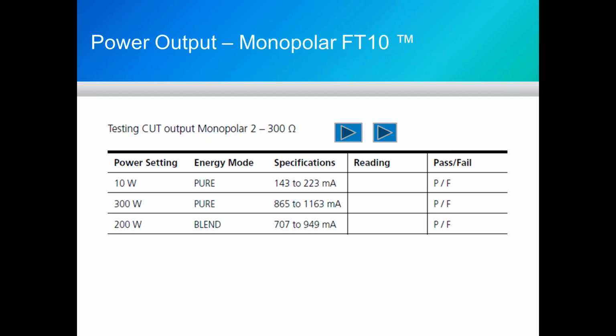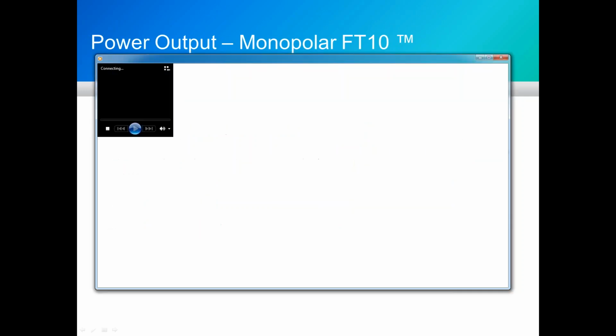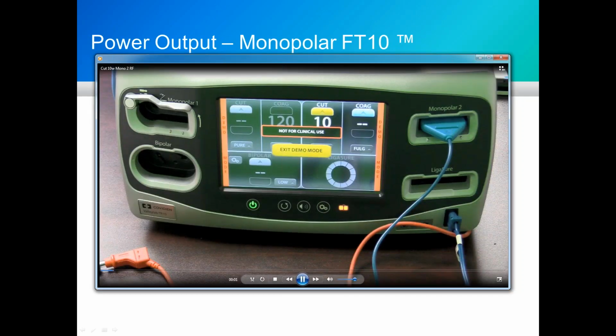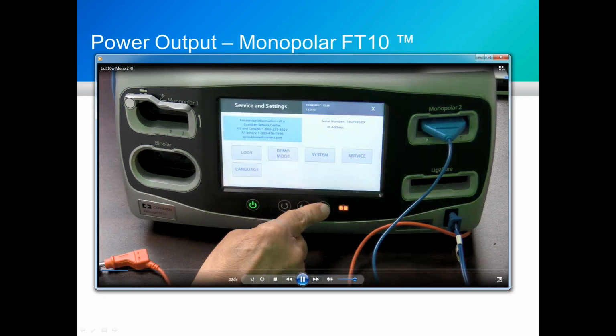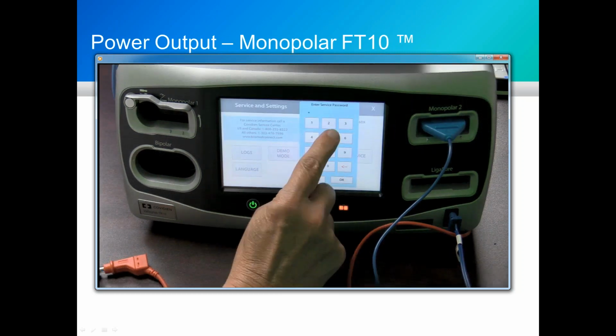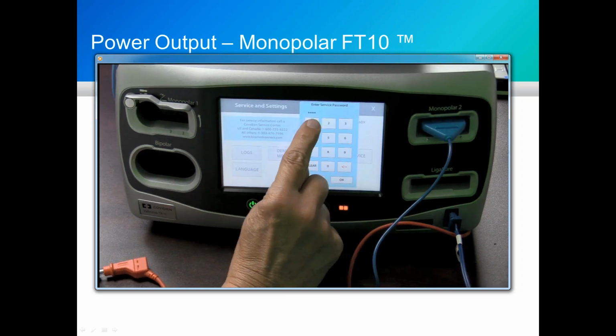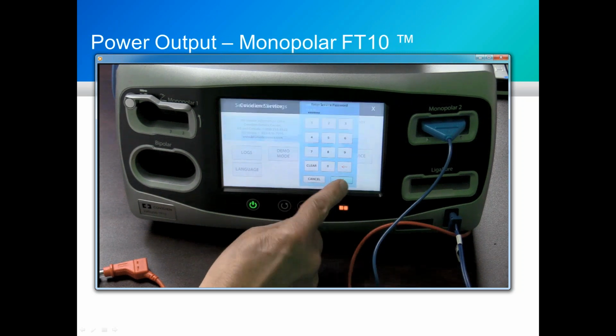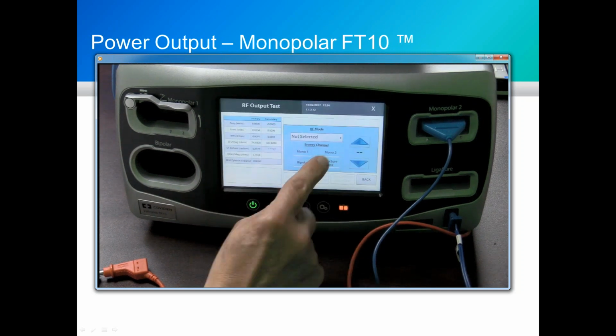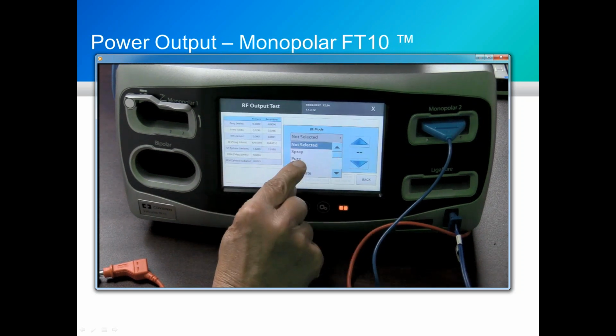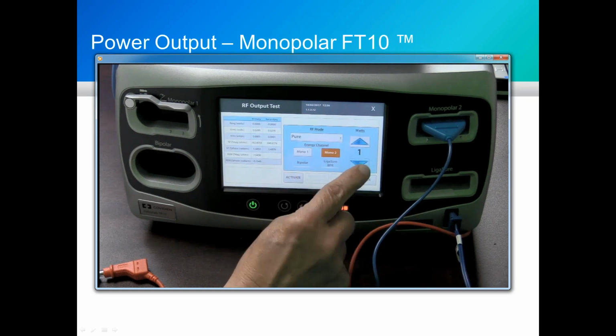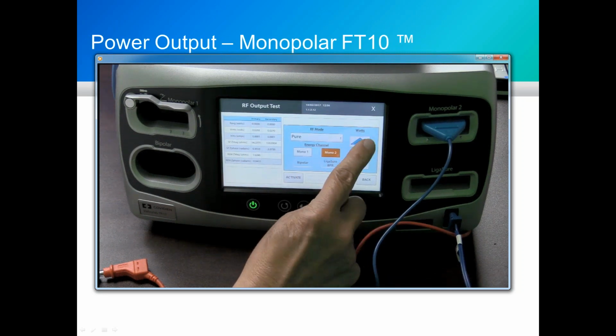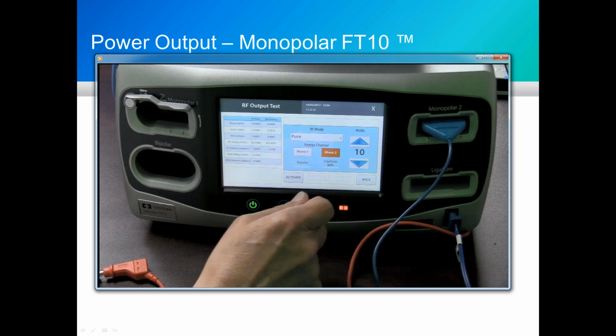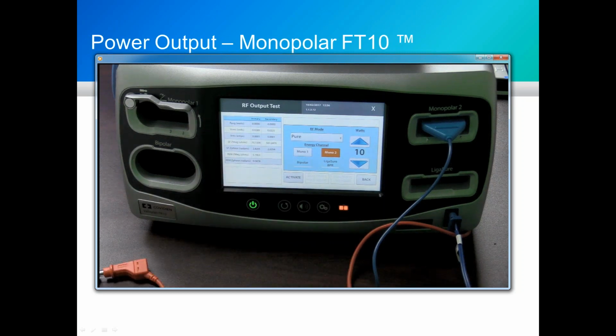Now we're going to do the same test in RF mode. This requires a little bit more interaction between you, the biomed, and the unit itself. So again, we have to go into service mode, enter the password, RF output test, select our energy channel, our output port, and the power.